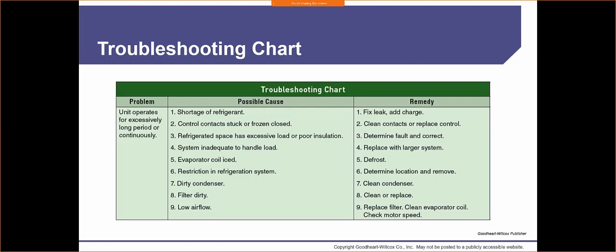On initial startup, when we first turn the power switch on the side of the unit. Each unit has, or should have, a little light switch somewhere around it to turn the system on or off. It's there for us technicians to work on the system. When we turn that switch on for the first time, the blower motor will either turn on or it won't. Different manufacturers have different parameters on that. The reason the blower motor turns on is the board doesn't know if the system was just operating and there was a power failure. It may have been in the middle of a heating cycle, with gas or heat inside the heat exchanger, so it's just going to cool off that heat exchanger first to get everything nice and primed, and then it'll fire up. Other systems don't care. So the blower motor first turns on, or it doesn't.